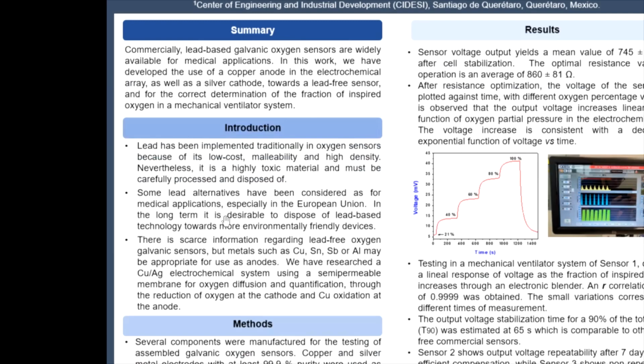For the introduction, we know that lead is a very malleable metal, also very low cost and has a high density, and it has been traditionally used in oxygen sensors. The high density is important because we can use a small volume of lead but still have a high lifetime potential of the sensor. Nevertheless, as you all know, lead is highly toxic, and in a manufacturing process we have to be very careful of contamination. Also, when the sensors are being disposed of, we need special handling.